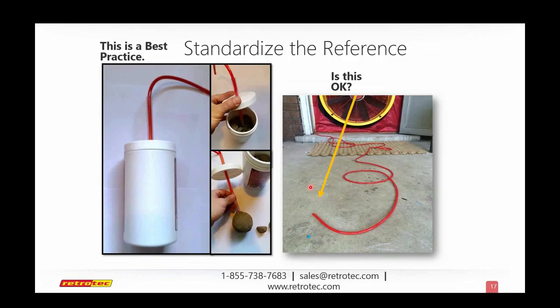So it looks like there's an advantage in testing over a wide range. In fact, there isn't. We make our ranges very, very close together so that there's a lot of overlap between gauges. Not all manufacturers do that. Most of them just have maybe a few percent overlap. We have like 60, 80% overlap. So you do have the ability to test an entire test in one range, which I think is a better idea. I would say for the kind of test that you're doing, if you tested from, let's say, 30 pascals to 60 pascals on a regular basis, if you're looking for results at 50, you would consistently get more repeatable results than testing from 10 to 100. So there's my point there.